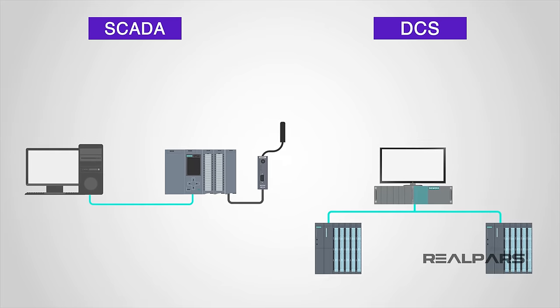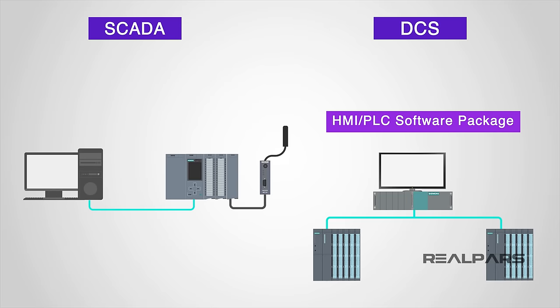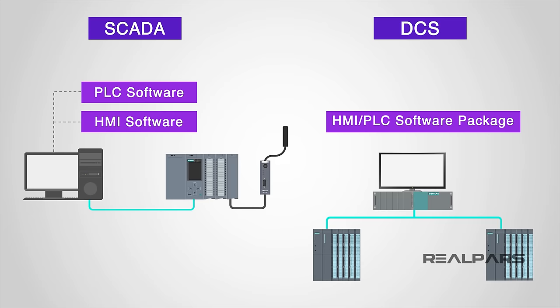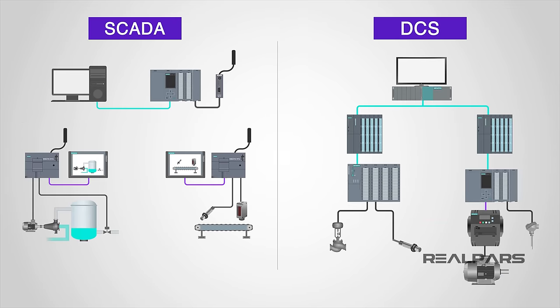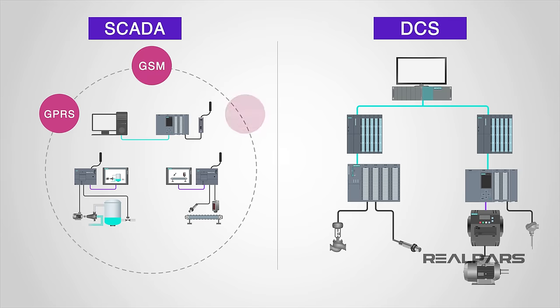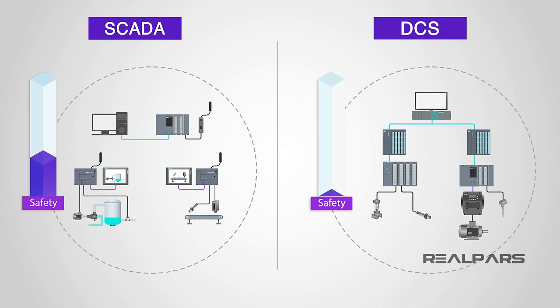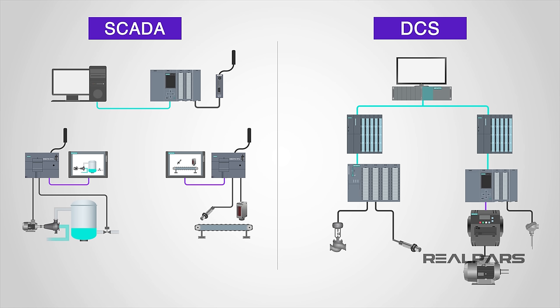To sum things up, in today's market there are not massive differences between the systems. DCS systems have integrated operator interface software with tag databases, while SCADA requires you to purchase additional software and build or import your tags. If you have a very time-sensitive process, SCADA systems may have a slight advantage as processing time is faster. Need an open communication architecture? Advantage SCADA. Concerned about safety? Advantage DCS. There are a lot of similarities between the two systems, and hopefully this video has shed some light on both the similarities and differences.